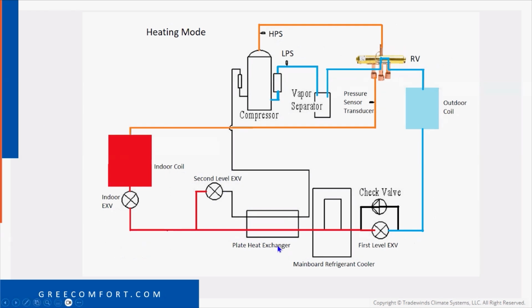So, and we'll kind of go back to that in just a second. Again, our liquid refrigerant's going to our main board to cool the main board, and I can show you that as well. And then we go through our primary EEV outside now, which is our first level EEV. The outdoor EEV is actually metering the refrigerant, and this check valve's closed, so we're forcing all the refrigerant to meter through the EEV, flashing the refrigerant into the outdoor coil.